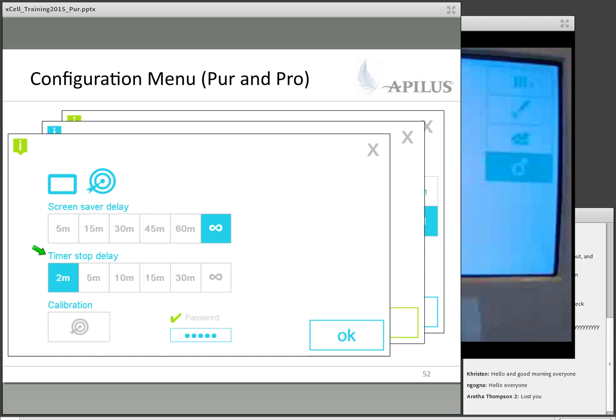One thing that happens though is that when you're doing cataphoresis, because you're not using the foot pedal, it also senses that as you being gone, and so it will pause the timer while you're doing cataphoresis. And that can be frustrating because I leave for 5 minutes and sometimes I just wait for the ding ding of my timer to go off in order to stop. And every once in a while if I have this on, the timer will stop on its own and I'm just going away doing cataphoresis and then wondering why is it taking so long? And then I look back and I see my timer's paused.